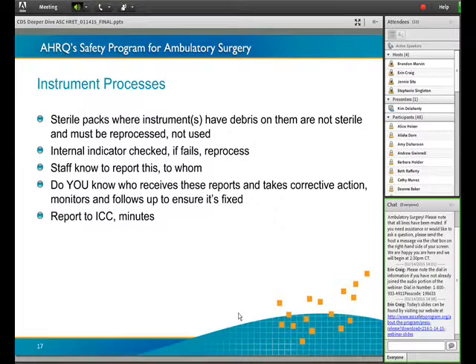The internal indicator I just talked about—you have to check if it failed or if it's reprocessable, if it shows it meets that requirement. We put all the indicators and integrators, since there are two, on a storyboard up in the sterile processing department so you can see what is positive and negative, what is fail and what is appropriate. The staff need to know it's okay to say, I'm sorry, but this doesn't meet that, even if it's at the sterile field, because that's going to save the patient from having any adverse outcome.